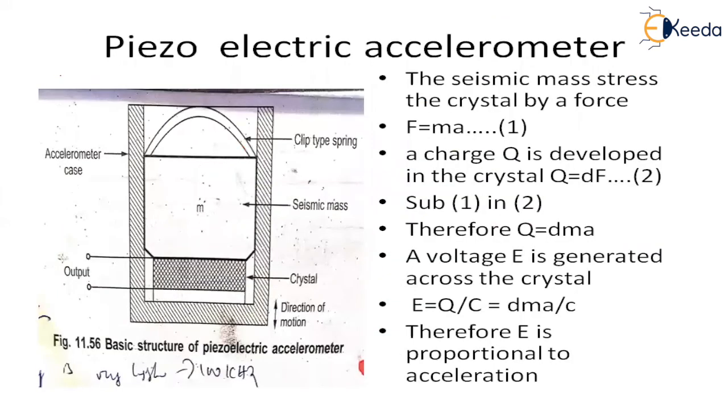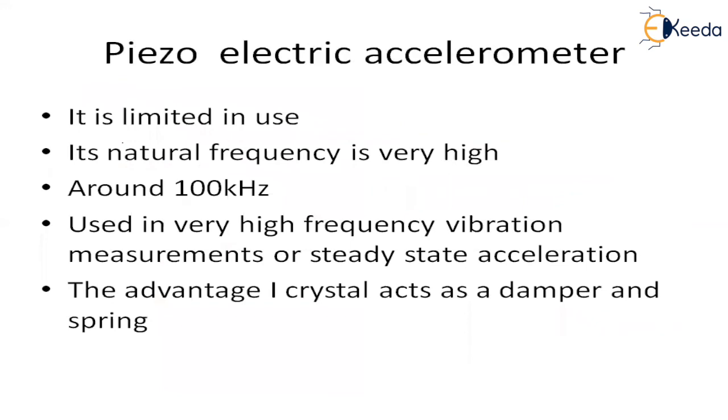For the piezoelectric accelerometer, a piezoelectric crystal is used. According to its features, its natural frequency is very high — around 100 kilohertz — so it is used for very high frequency measurements or steady state acceleration. The advantage is that the crystal itself acts as both a damper and a spring.